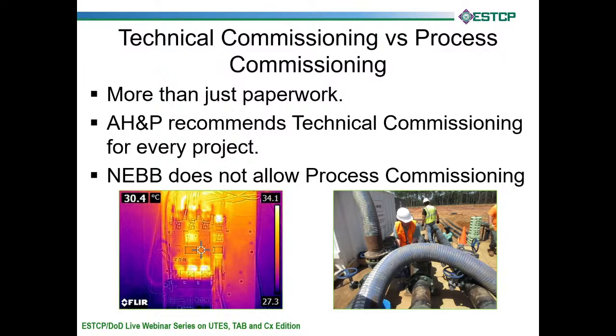It is a very hands-on approach of testing each piece of equipment, like we said previously, and especially with controls, verifying the entire sequence of operation. So it also doesn't allow any sampling strategies. We feel like every piece of equipment needs to be tested. For the most part, with things like grills, if you're verifying grills, we do some sampling strategies on that. But as far as testing the mechanical equipment, we don't believe sampling strategy is a good approach. NEBB doesn't allow process commissioning. They only allow technical commissioning.